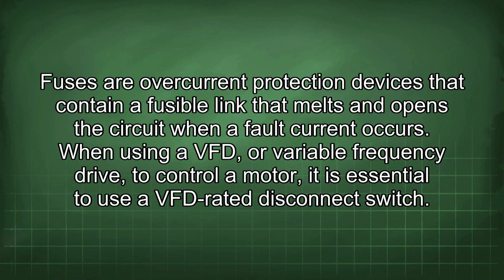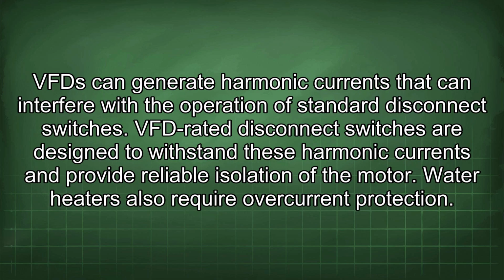When using a VFD, or a variable frequency drive, to control a motor, it is essential to use a VFD-rated disconnect switch. VFDs can generate harmonic currents that can interfere with the operation of standard disconnect switches. VFD-rated disconnect switches are designed to withstand these harmonic currents and provide reliable isolation of the motor.